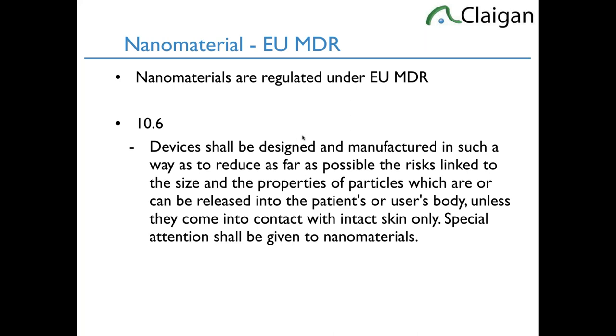You need objective evidence that your regulatory group, external auditors, and notified body are all comfortable with. Normally they want a document they can point to that addresses nanomaterials — where in your tech file does it show you addressed nanomaterials? There isn't one prescribed way to handle it. There are a variety of options since, as is true for a lot of MDR, as long as you address it and the notified body agrees, that works.